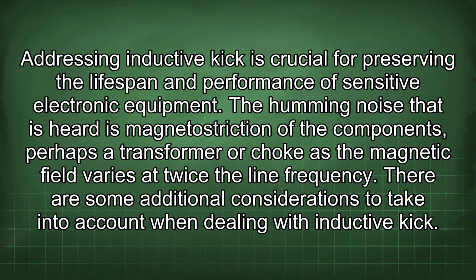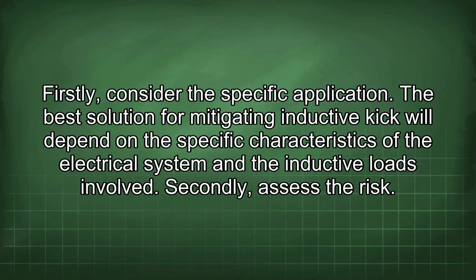The humming noise that is heard is magnetostriction of the components, perhaps the transformer or choke, as the magnetic field varies at twice the line frequency. There are some additional considerations to take into account when dealing with inductive kick. Firstly, consider the specific application. The best solution for mitigating inductive kick will depend on the specific characteristics of the electrical system and the inductive loads involved. Secondly, assess the risk.